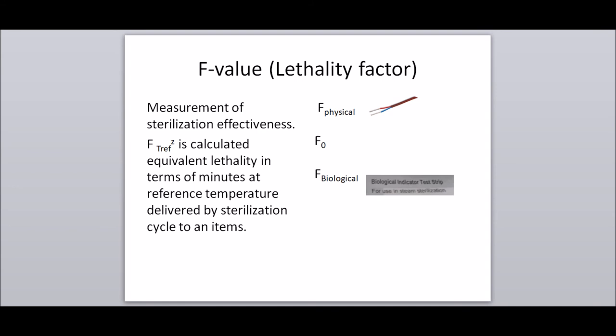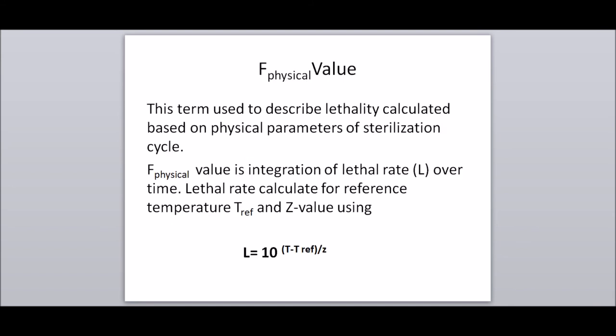We will see what is F physical, F zero, and F biological. F physical value: this term describes lethality calculated based on the physical parameters of a sterilization cycle. F physical is the integration of lethal rate L over time. Lethal rate is calculated from the reference temperature T-reference and Z value using the formula: L = 10 raised to (T minus T-reference) divided by Z.